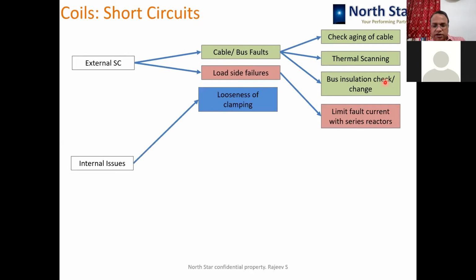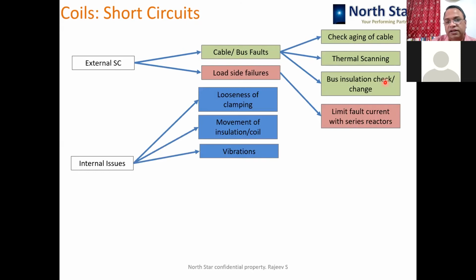Internal issues: there are several issues in the transformer that can be because of a manufacturing defect, or can occur because of the service condition of the transformer, that is looseness in the winding, coil movement in the transformer, severe vibrations. All these effects can be checked by conducting SFRA testing, which can tell you that everything is right inside the transformer and no movement, vibrations or looseness has happened.